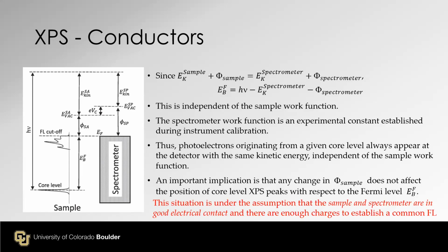So once it's established, we can use it for the same value. But I think during the annual preventive maintenance period, they may check. Is that calibration done during every run? No, it's annual, whenever they come in for the annual checkup. So once it's established, we don't see this spectrometer work function value. It's hidden somewhere in the system. That's not our job to calibrate this value.